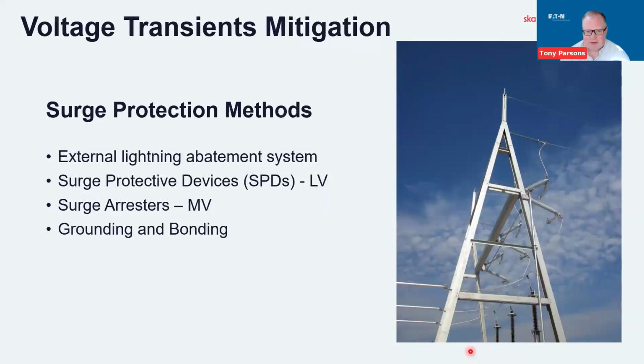As far as solution methods, if we're talking about lightning, we've got special lightning abatement systems that we can design and deploy. The picture on the right-hand side shows, up at the top of the structure, some lightning rods or strike termination devices. That's a 138 kV transmission tower, but you see those on buildings and other installations as well. Inside the building, surge protective devices or surge arresters. With all of these things, what they're trying to do is provide an alternate path for that high energy to travel. Instead of letting it affect our equipment in the building, we want to give it a path to ground or earth. So the grounding and bonding, or the earthing system, is an important part of your transient mitigation. People sometimes overlook that, but if you don't have that low impedance path for that energy to travel, you're going to increase the likelihood of problems with the equipment that you want to protect.